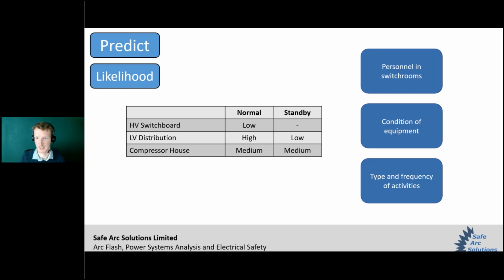So just to pick out a couple of examples in the table at the moment, maybe the high voltage switchboard is a new switchboard. It was only installed last year, and it's installed in its own switch room, which is locked and inaccessible to anyone other than those authorized to go in there. So you might consider that to be a low likelihood of an arc flash happening and impacting people. Whereas the LV distribution switchboard is sitting in a much more populated area of the site. There are more people coming and going, and generally more tasks happen on that switchboard. So you might consider that to be a higher likelihood of an arc flash happening.